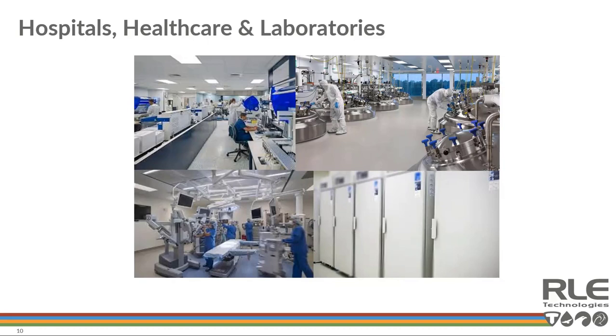So the story goes, it wasn't long, a few weeks later, the gentleman who was actually kind of holding off on the approvals, trying to justify spending the money, had a black water pipe rupture above his office and rain down through it. Underneath his office, on the next floor down, were some blood analysis machines. It actually ended up taking out a couple million dollars worth of blood analysis machines. What the quote originally was, about 8,000 or 9,000, ultimately ended up being a little less than $20,000 worth of leak detection installed at that site.